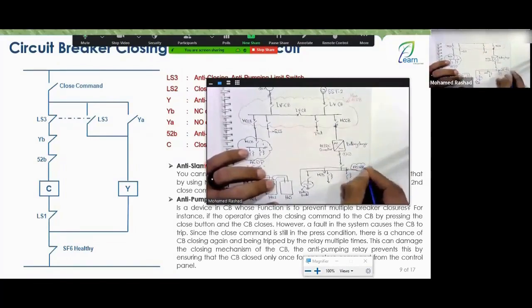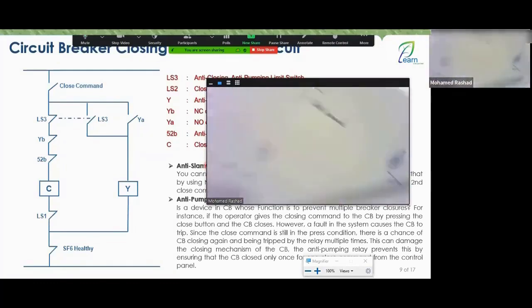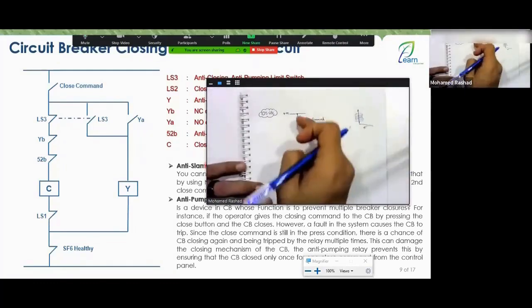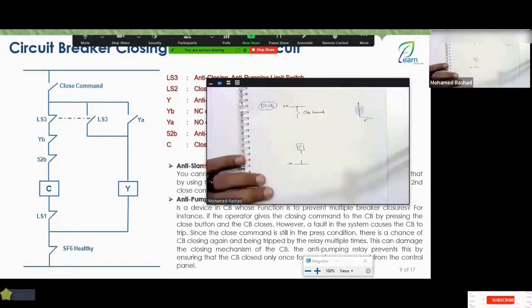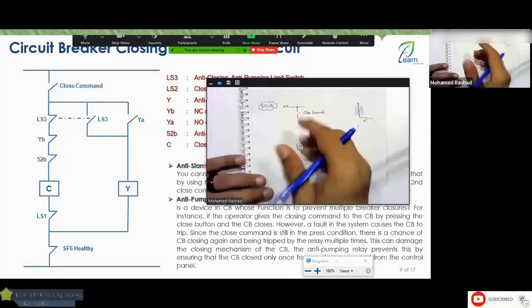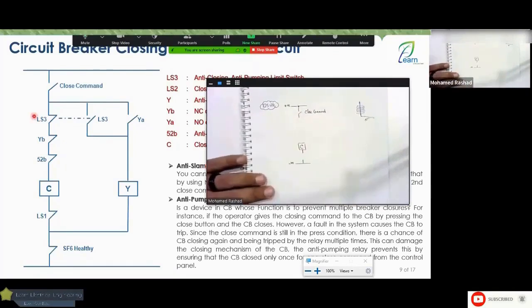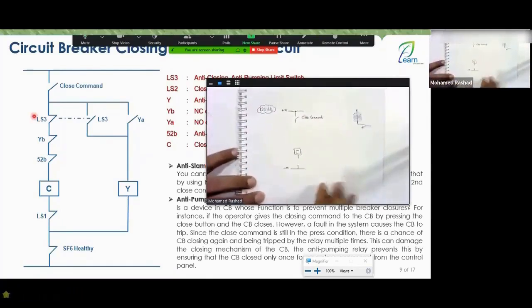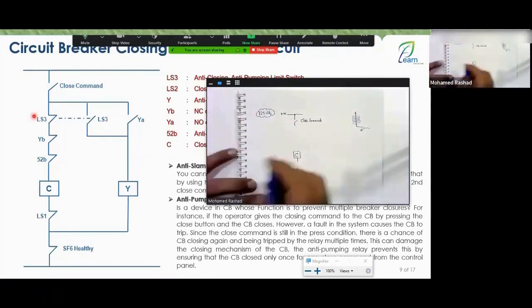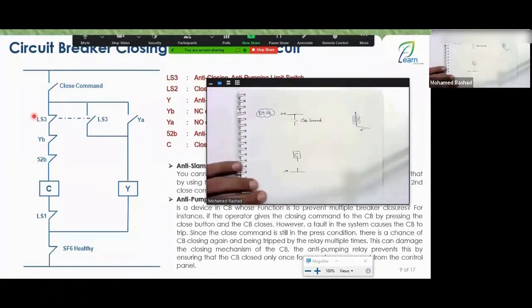Now the closing coil, engineer: if you apply 125 VDC to it, it draws current. This current depends, of course, on the size of your circuit breaker, whether it is medium voltage, high voltage, or extra high voltage. So it will draw a certain amount of current. If it draws this current for a longer period, it will overheat, all right?